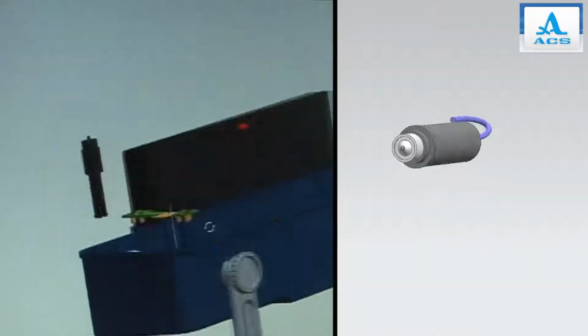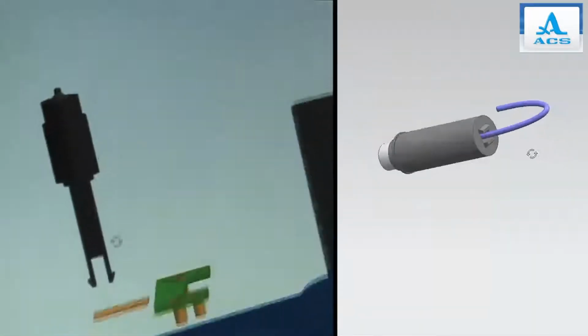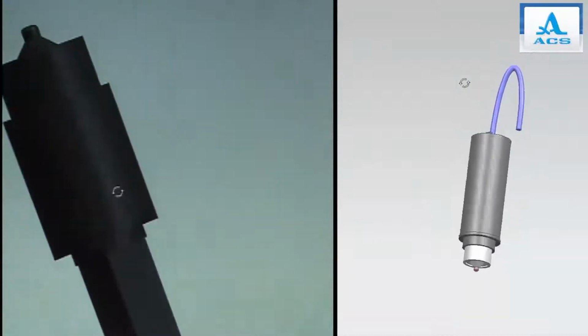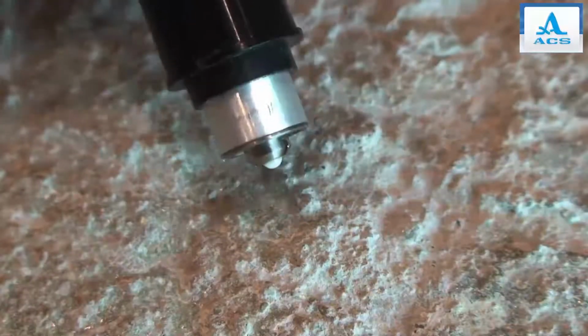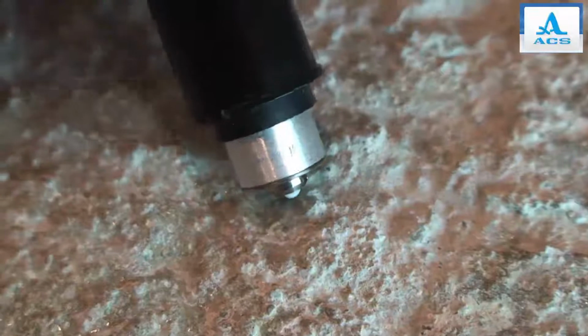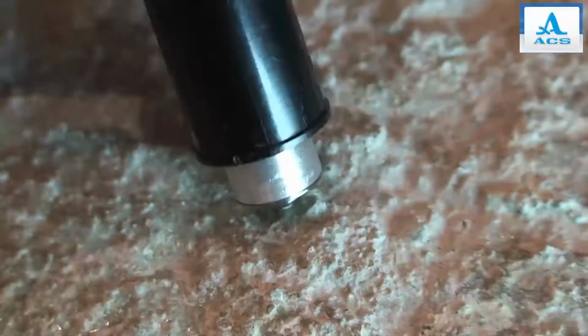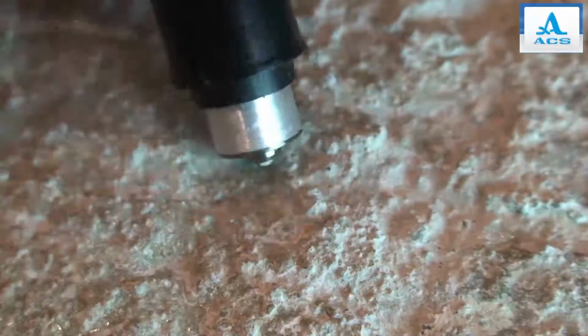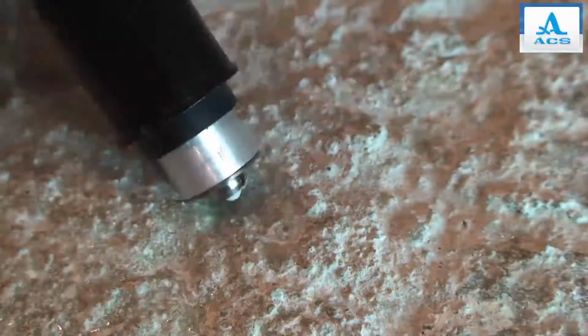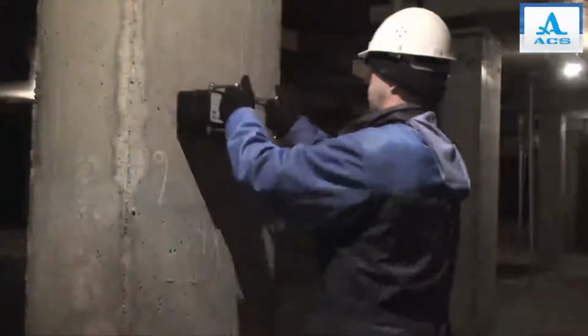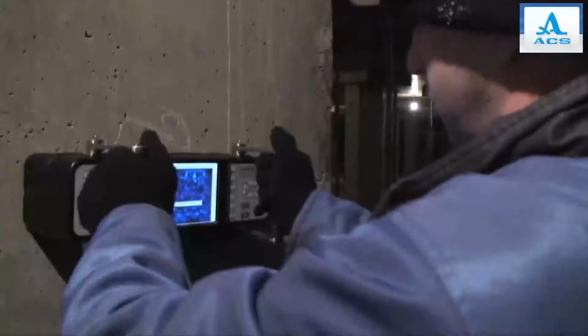The dry point contact ultrasonic transducers used in the MIRA instrument are constructed with a proprietary crystal tip and a high-performance composite damper housed in a very small casing. The actual contact surface area of the transducer's tip to the face of the test sample is so small that a coupling agent is no longer required.